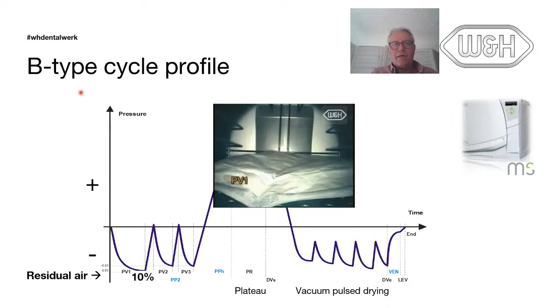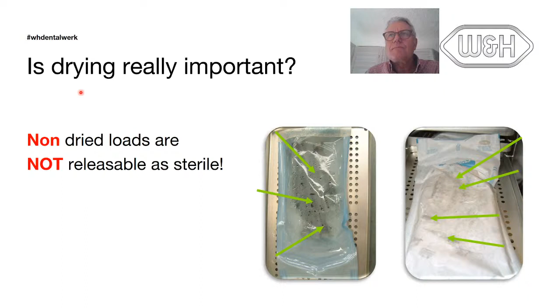Sorry, it's a bit technical and we have to rush. They also dry very nicely. See, this is absolutely not acceptable. The paper must be absolutely dry and you must not see any droplet on the plastic side. So this is not acceptable. And this is how we would classify the steam sterilizers. These old machines from the previous century, 2 centuries ago, are not so interesting. They have no vacuum, no drying, nothing. So let's focus on B cycle or specific cycle like our MS.